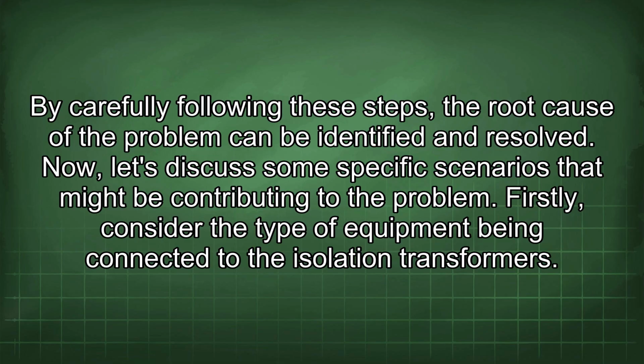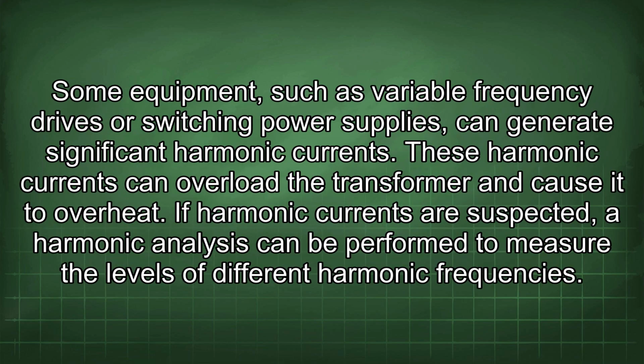Now let's discuss some specific scenarios that might be contributing to the problem. Firstly, consider the type of equipment being connected to the isolation transformers. Some equipment, such as variable frequency drives or switching power supplies, can generate significant harmonic currents. These harmonic currents can overload the transformer and cause it to overheat. If harmonic currents are suspected, a harmonic analysis can be performed to measure the levels of different harmonic frequencies.